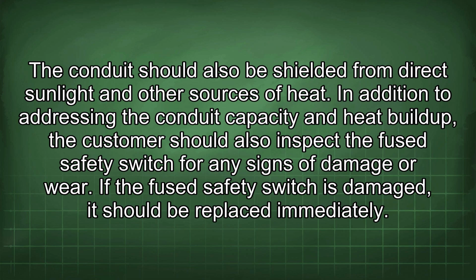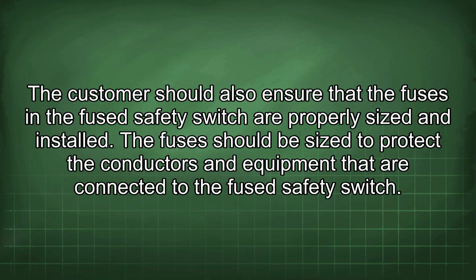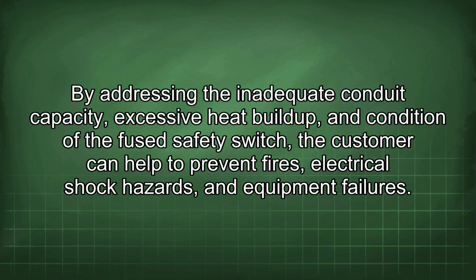In addition to addressing the conduit capacity and heat buildup, the customer should also inspect the fused safety switch for any signs of damage or wear. If the fused safety switch is damaged, it should be replaced immediately. The customer should also ensure that the fuses in the fused safety switch are properly sized and installed. The fuses should be sized to protect the conductors and equipment that are connected to the fused safety switch. By addressing the inadequate conduit capacity, excessive heat buildup, and condition of the fused safety switch, the customer can help to prevent fires, electrical shock hazards, and equipment failures.